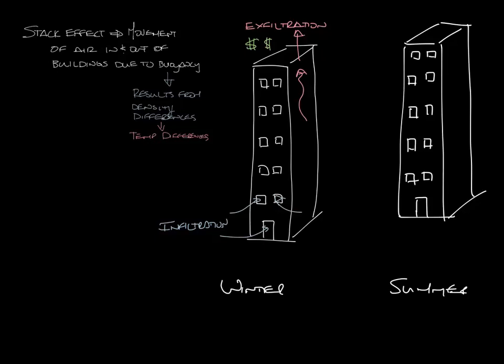In the summer, stack effect still happens, but the air inside the building is colder and denser than the warm outside air. So you get what's called a reverse stack effect — warm air is drawn into the top of the building and exits out the bottom of the building as the cold air falls.